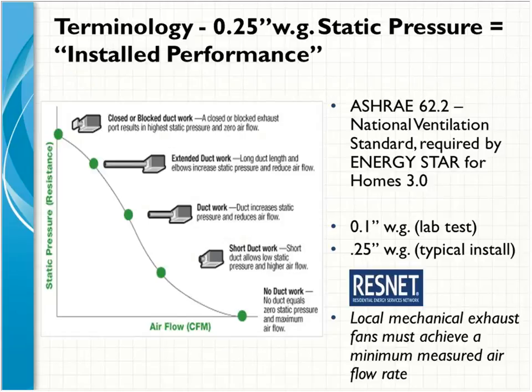And as the chart here shows, as you increase the static pressure, the airflow will generally decrease. So HVI will test the equipment for bathroom fans at 0.1 inches of water gauge. But that's often not a realistic install. How many of our audience does actual install work? Is there anybody that I can ask a question of that's doing actual installs of bath fans or HRVs, ERVs? Generally speaking, what I would do is ask the audience, is 0.1 inches of water gauge a realistic install?